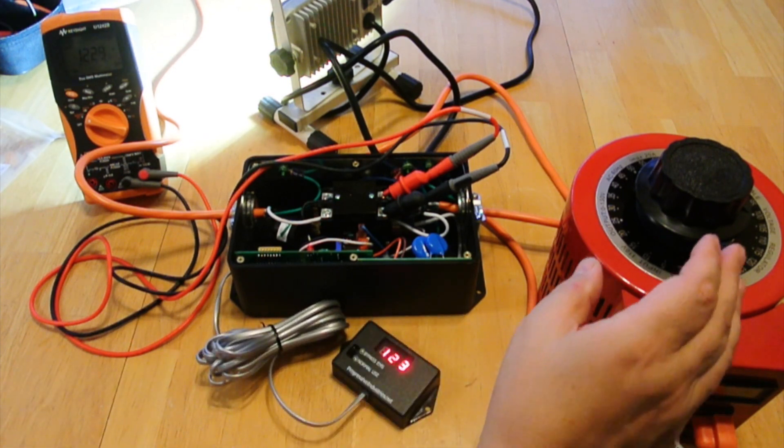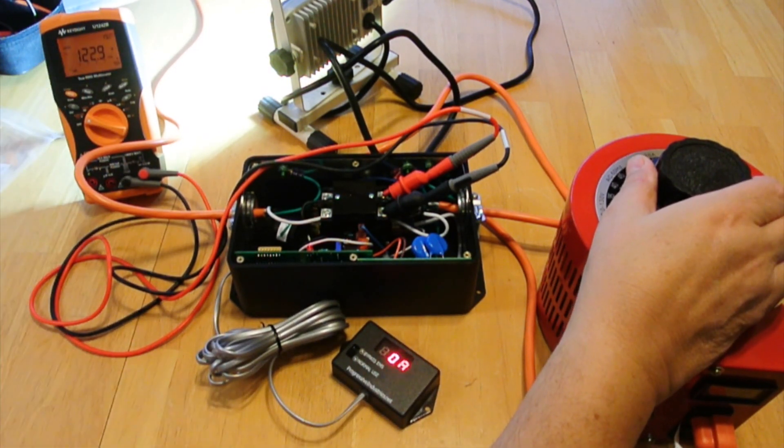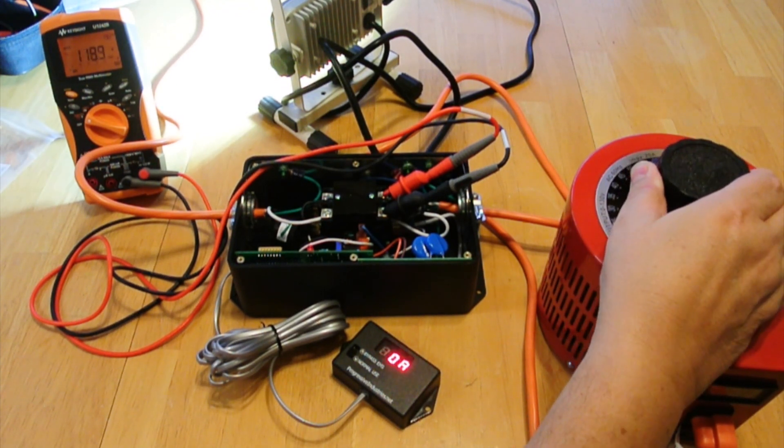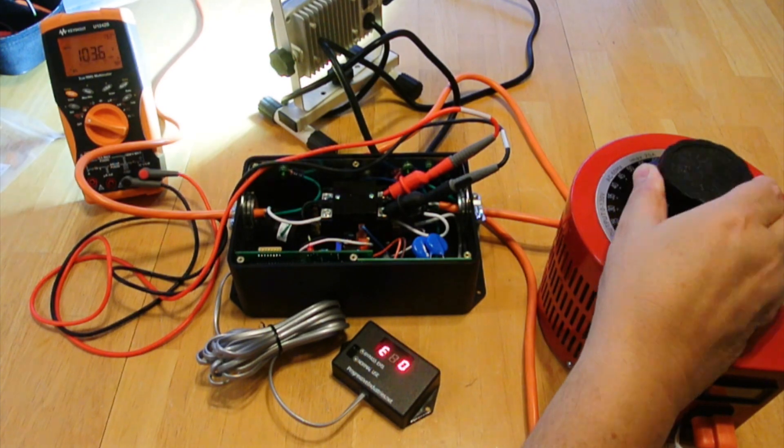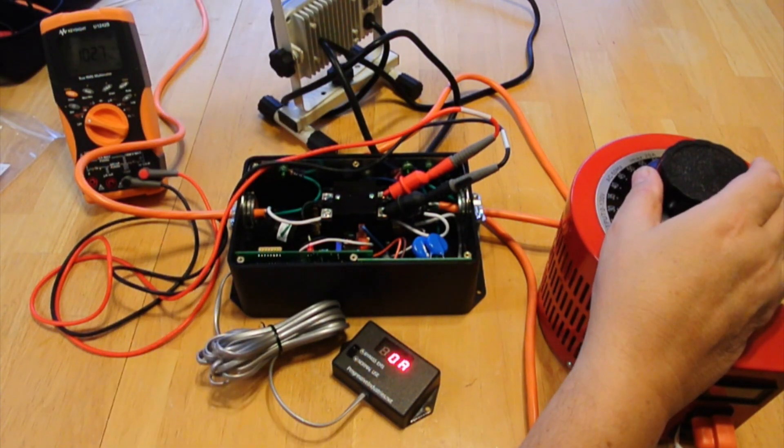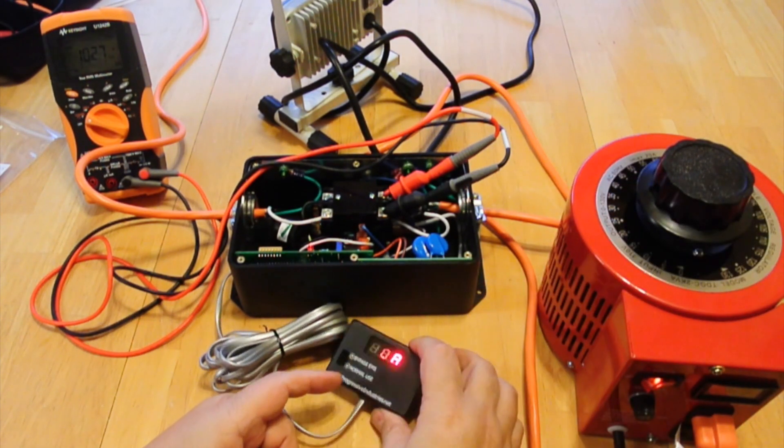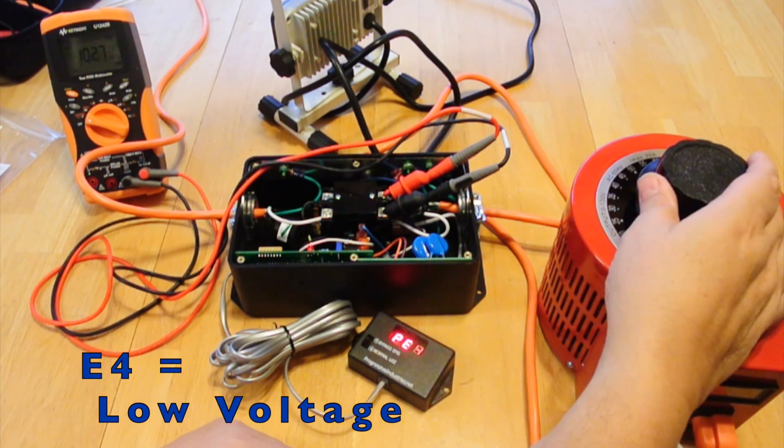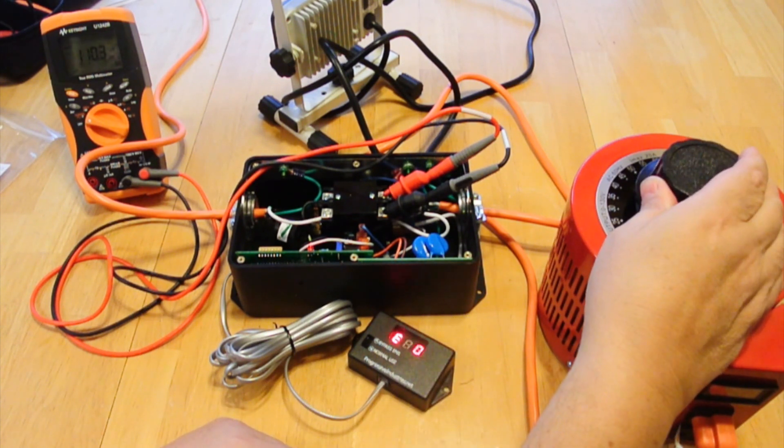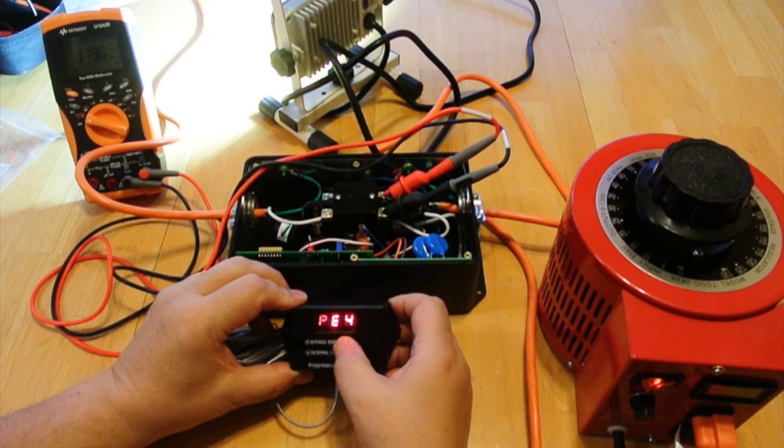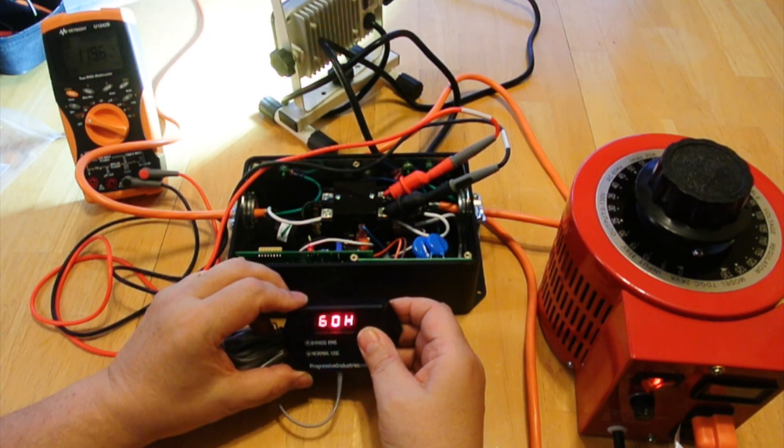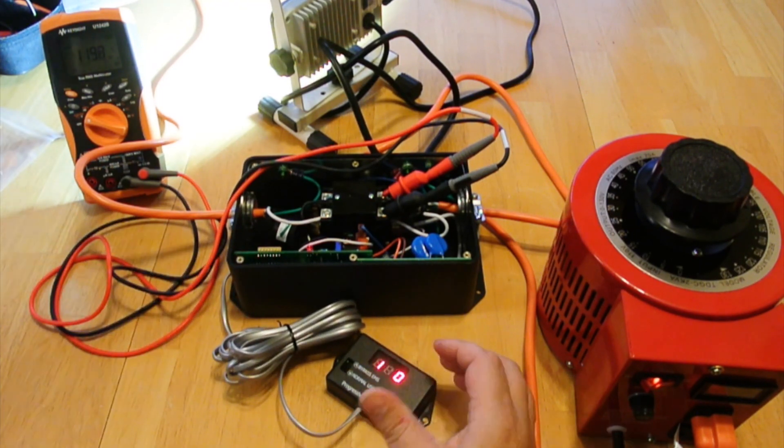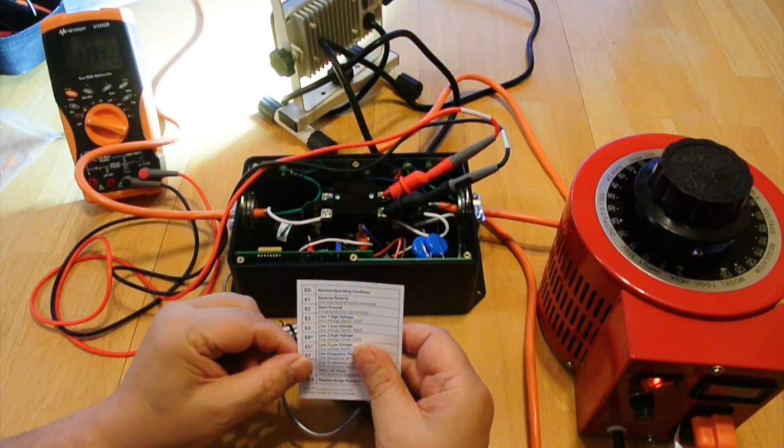Now we're going to take our auto transformer, and then we're going to look at our voltmeter, and we're slowly going to turn it down until we reach 104 volts. Okay, we're below 104 volts, and it turns the power off. And we also get E4. E4 means error 4. Now we're going to bring the voltage back up above 104 volts. And you'll see now that we have a PE4 error. PE4 error means previous error, and 4 again from the chart we have. E4 error 4 is line 1 low voltage.